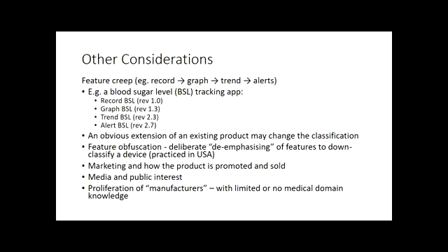And that red example where I said, put a warning in that says this is used for interpretation only and shouldn't be used as a diagnostic tool. A lot of people use that, de-emphasize the features in order to not have to deal with a classification system. So it's a lot easier to say, even though it has all these components, we're just going to try and market it as a non-medical device because we don't want to go through the conformity assessment process. So it happens a lot.